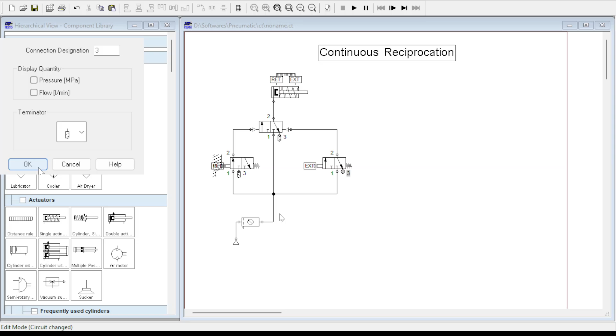Now let us try to understand the actuation. I'll press the start button. The cylinder is in the retracted position. The main DCV shifted its position and the cylinder has extended. And after extending, the extension limit switch will sense it and it will give the pilot signal to the right side actuation, and it will cause the cylinder to retract because of the spring force.